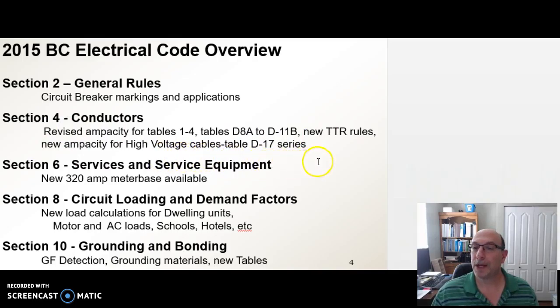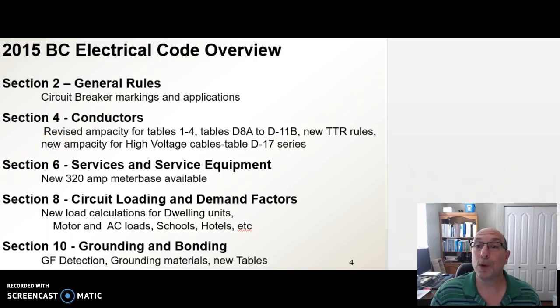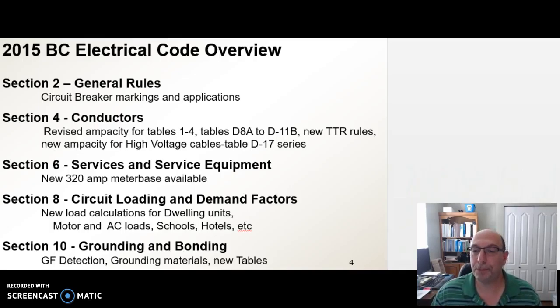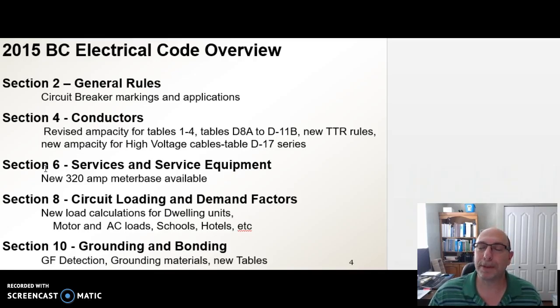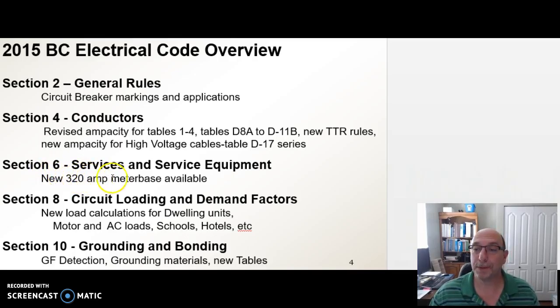We finally have ampacities for high-voltage cables in Section 4. For those installing high-voltage cables underground and wanting to know the ampacities, use the D17 series. Big change in Section 6: the 320-amp meter base is now available. For installations with high demand loads — such as vehicle car chargers, single-family dwellings with multiple suites — where you don't want to install a 400-amp service, you can get away with a 320-amp meter base.